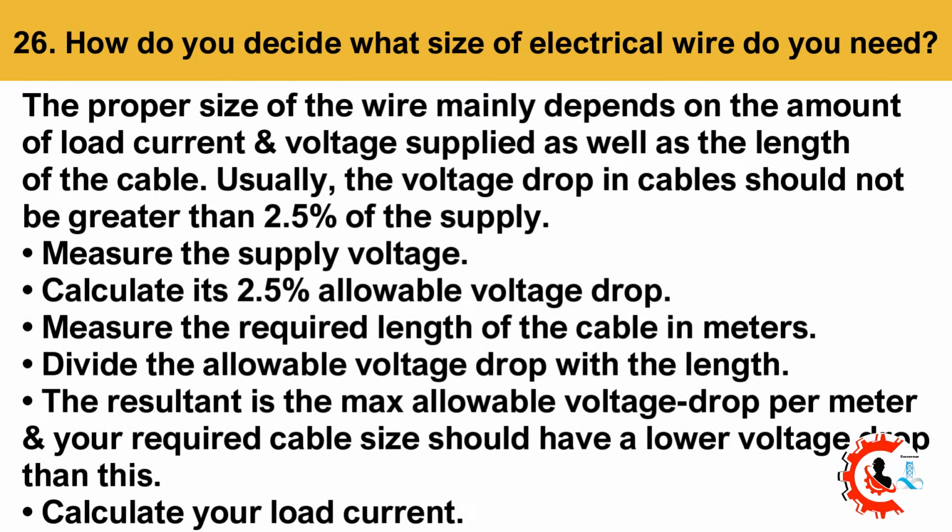26. How do you decide what size of electrical wire you need? The proper size of the wire mainly depends on the amount of load current and voltage supplied as well as the length of the cable. Usually, the voltage drop in cables should not be greater than 2.5% of the supply. Measure the supply voltage. Calculate its 2.5% allowable voltage drop.